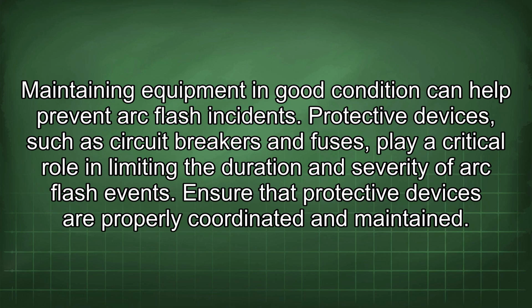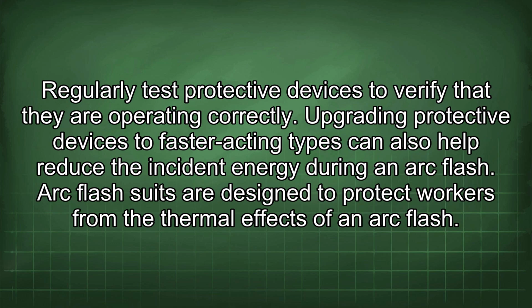Protective devices, such as circuit breakers and fuses, play a critical role in limiting the duration and severity of arc flash events. Ensure that protective devices are properly coordinated and maintained. Regularly test protective devices to verify that they are operating correctly. Upgrading protective devices to faster acting types can also help reduce the incident energy during an arc flash.